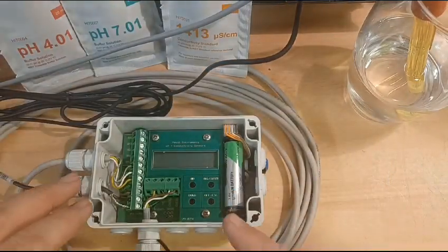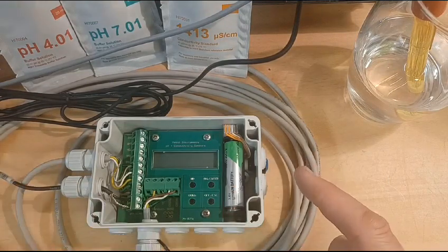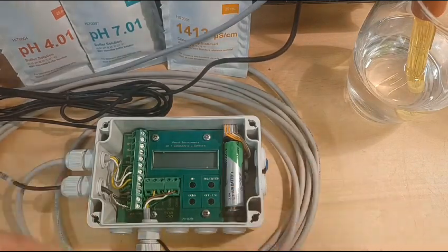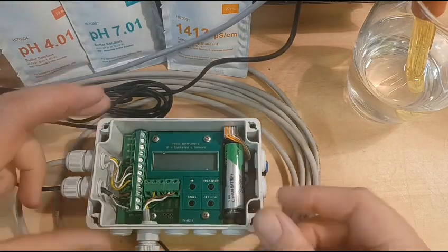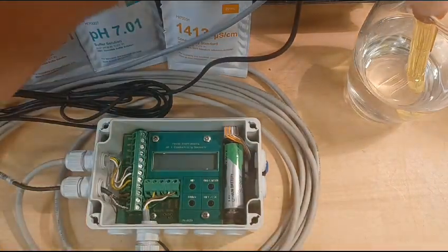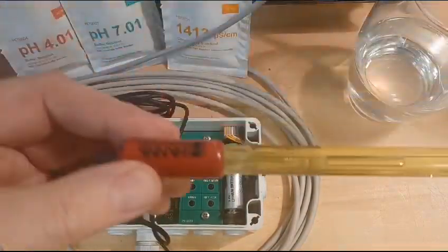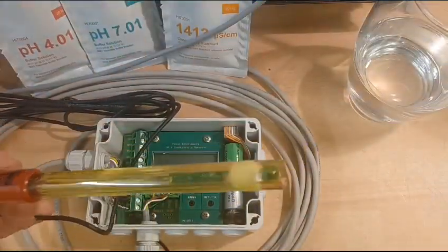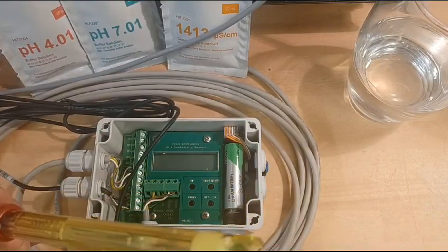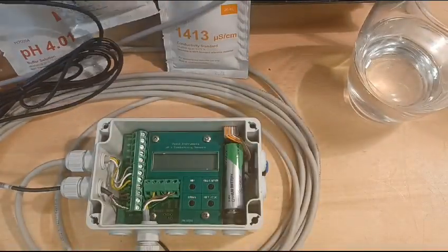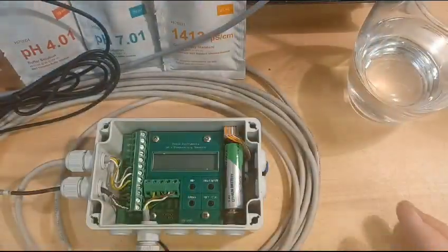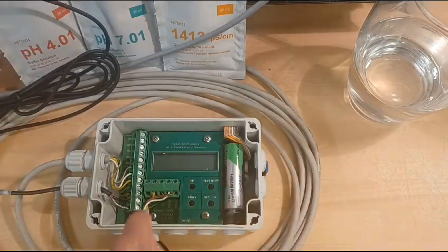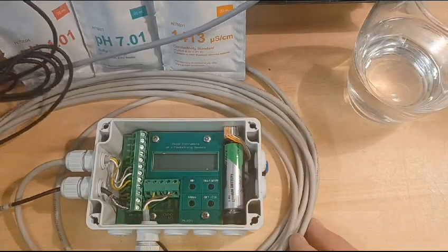Now I'm going to video the calibration, but I will pause while it's waiting, because sometimes it does it quite quickly, sometimes it takes a while, and obviously I'm limited on the size of the video. So we'll do pH first. Your pH sensor, without the shield on now, so you can see that's the actual sensor inside, goes into the pH solution 7, like so. Stand this upright somewhere. In the field, when this is all connected, you can stand this next to the tipper in between. It stays perfectly there.